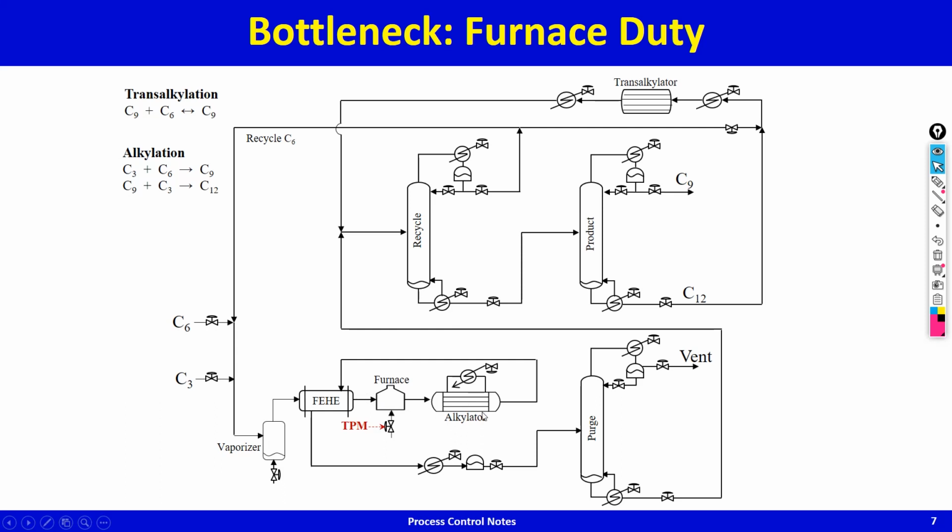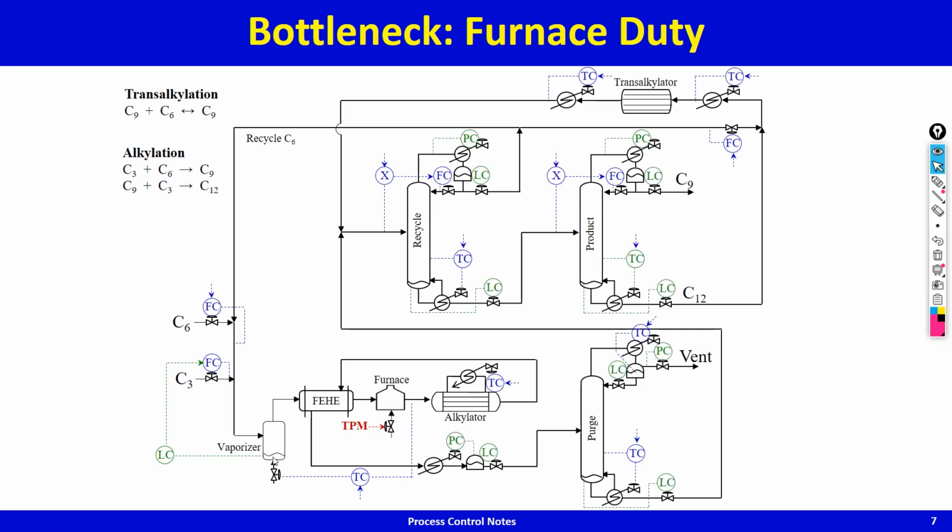How do you adjust the flow here? Well, the flow here gets adjusted by boiling off more. So you will have a temperature controller that does this, and this will be a reasonably fast loop. Now given that this is done, how do you control the level of the vaporizer? Same as before. Everything else is the same. You've got the same economic loops, and of course I must emphasize this ratio controller should be on always, otherwise you'll have problems in level control here, because if this flow is too large compared to this flow, this level cannot be controlled by just this guy.